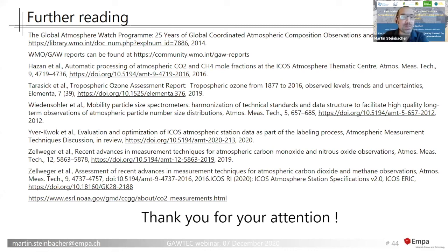Well, if you have two measurement points, you can draw a line and then you have a trend. You measure once in 2010 and once in 2020, and then in theory, you could determine a trend. But the real answer is, it depends on the trend, on the strength of the trend, on the precision of your analyzer. For ozone, for example, it's about 10 years, I would say.